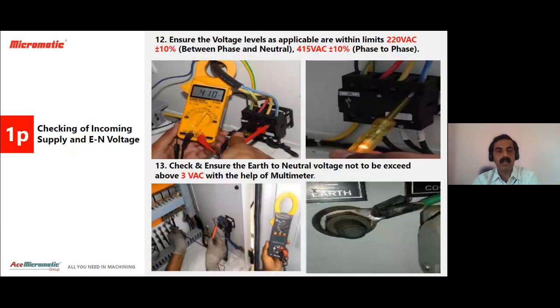Now the next is, after this we have to ensure the incoming supply as well as the earth and neutral voltage. The earth and neutral voltage must be checked. Also the phase to neutral, which is most important, must be 220 volt AC plus or minus 10%, and phase to phase is 415 volt plus minus 10%.